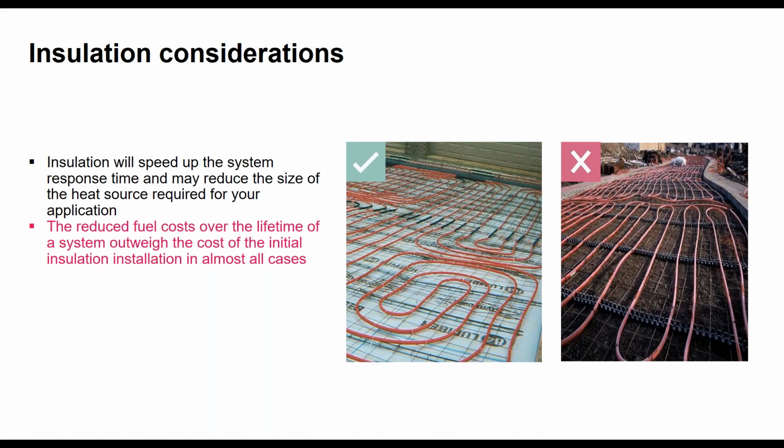I've also been involved in, and we're going to talk about some of these projects too, a hangar, an ice melt system in the track of a hangar door for an airplane type facility. In that case, this slab is very thick. You might be dealing with a 14-inch thick slab, and the slab's so thick that they pour it in multiple pours. So there's a 7-inch pour, and then the pipe goes down on the top of that slab, and then there's a topping slab that completes the full 14-inch slab, and our pipe is residing in the middle.